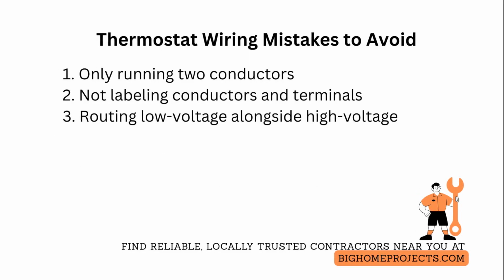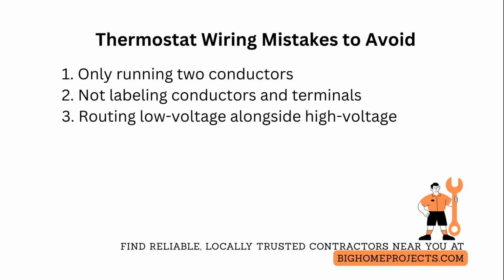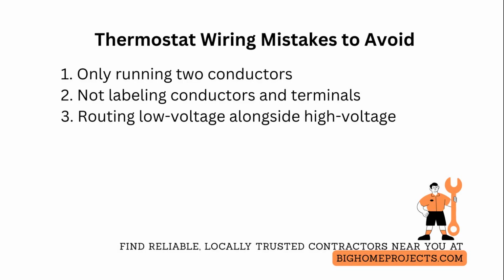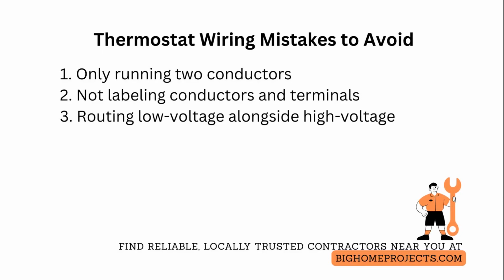One of the most common thermostat wiring mistakes is running just the 2 power conductors and later needing a common wire for a smart thermostat install. Fix this by pulling a 5-conductor cable now or installing a separate 24-volt transformer dedicated to the thermostat circuit.